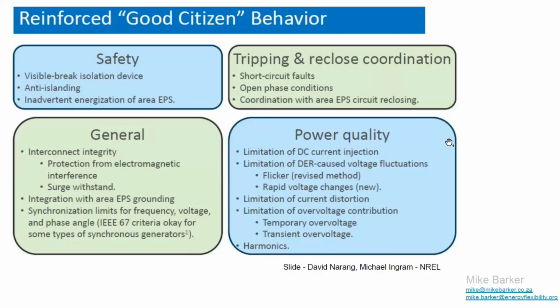The other good thing is we spoke about being a good grid citizen, and 1547 goes out of its way to support that. Safety is the first issue, we don't want to feed energy back into a dead grid. There's anti-islanding and a lot of good things that come out of that, plus tripping and reclosure coordination, which is pretty important. In fact, 1547 does a lot of good things and takes care of a lot of issues, perhaps some we haven't quite thought of just yet.